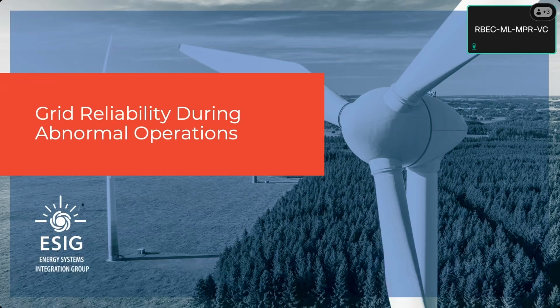Because if you look at the NERC standards, like the TPL standards, you're doing a 1 year out, 5 year out, 10 year out, and 2 sensitivities for your compliance assessment. So in a perfect world, every year you're doing next year's study with updates that happened in the year prior, and then you're catching those and projecting them out. But those depend on good models and good data.